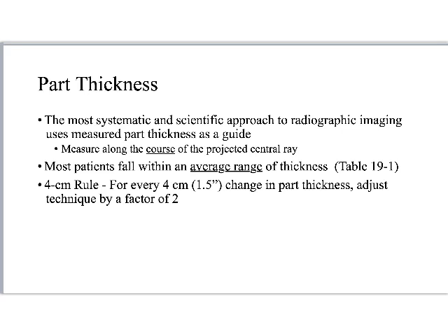So if I measure, for example, on the same patient a hand, and I'm also doing the elbow, right? And the hand measured at a 4 centimeter thickness and the elbow measured at an 8 centimeter thickness, I know that I'm going to have twice the mass from the hand to the elbow. So I already know what the elbow technique is if I have the hand technique. In essence, if I know what a hand technique is on this machine, I can compute technique for any other part of the body. That's a good power to have, right, as a technologist.